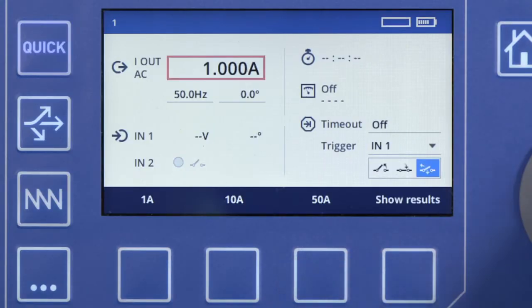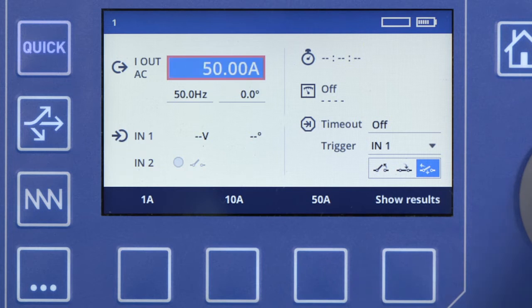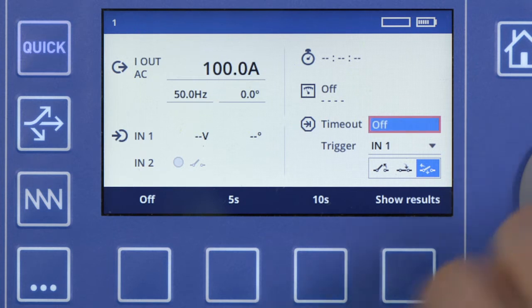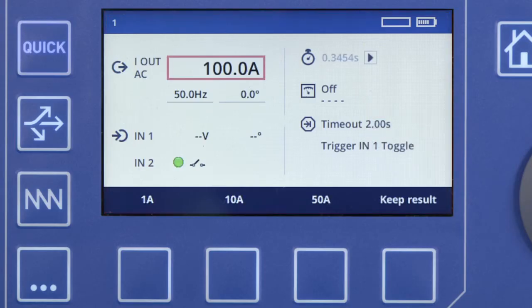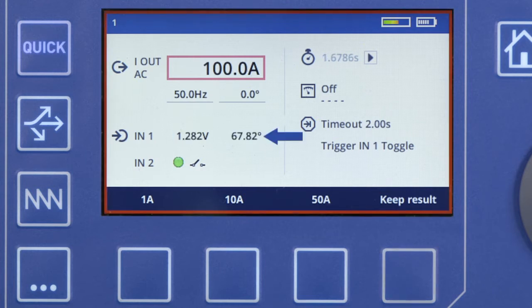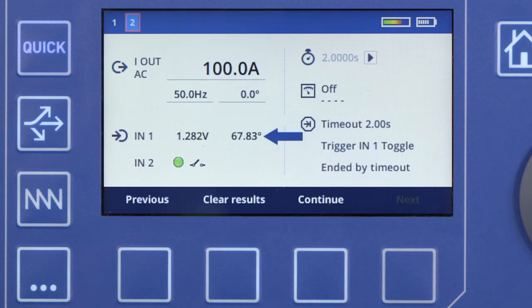Now we are ready to test the polarity. Please set a timeout of 2 seconds and then inject 100A into the CT. The phase angle displayed at IN1 is what we need to focus on now. It should be between 0 degrees and 90 degrees. The CT's polarity is correct.